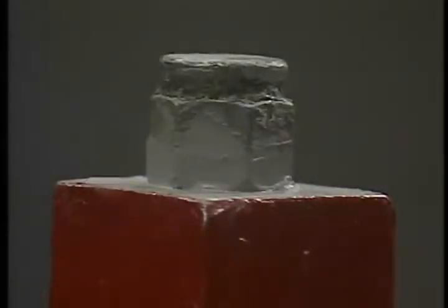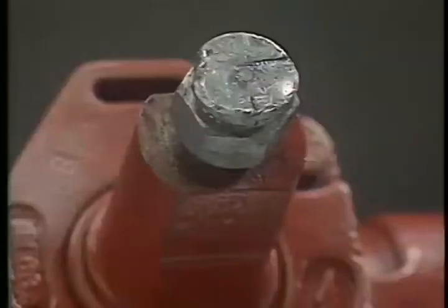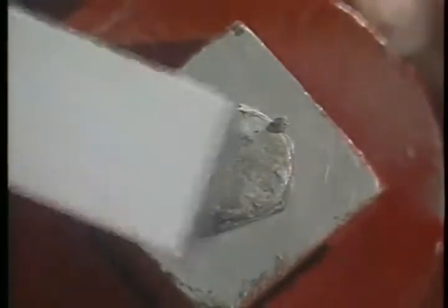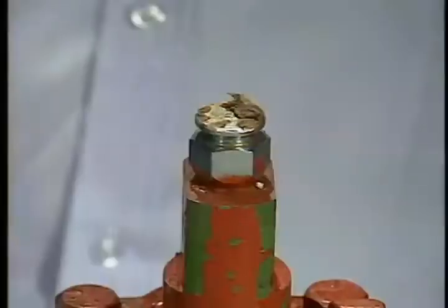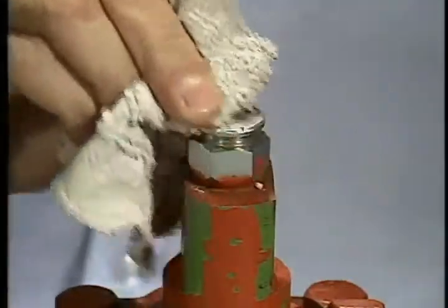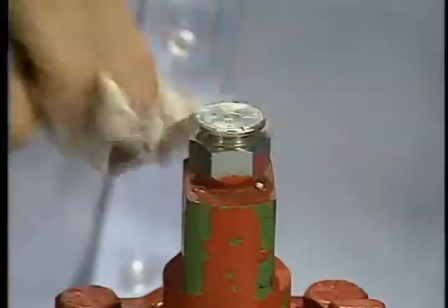Before lubricating any valves, the first step is to clean the face and groove of the valve sealant fitting and check for any damage that might cause it to leak or lose pressure. Fittings are generally exposed to the elements and often take a lot of abuse. First, remove any paint or dirt. If necessary, use a scraping tool or file. Be sure to wipe the fitting clean to be sure it's free of dirt and debris.